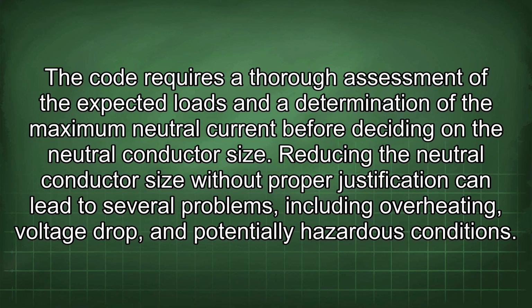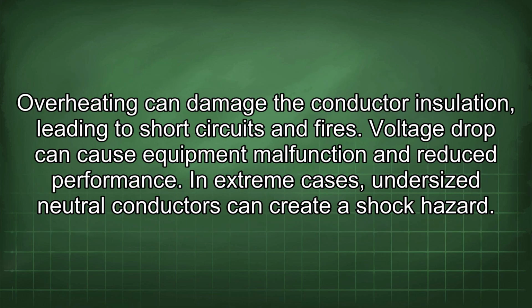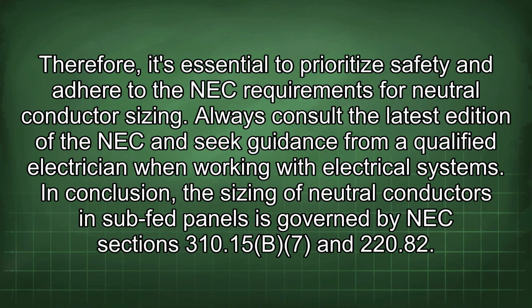Reducing the neutral conductor size without proper justification can lead to several problems, including overheating, voltage drop, and potentially hazardous conditions. Overheating can damage the conductor insulation, leading to short circuits and fires. Voltage drop can cause equipment malfunction and reduce performance. In extreme cases, undersized neutral conductors can create a shock hazard. Therefore, it's essential to prioritize safety and adhere to the NEC requirements for neutral conductor sizing. Always consult the latest edition of the NEC and seek guidance from a qualified electrician when working with electrical systems.